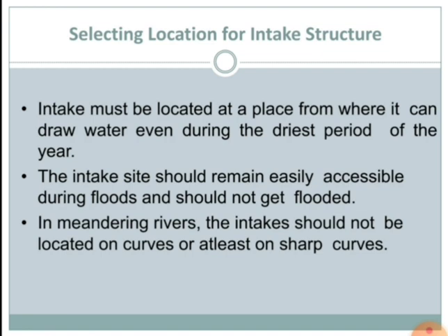Now, the intake site should remain accessible during floods and should not get flooded. This is again another important point to be considered. And also, in meandering rivers, the intake should not be located on the curves. If not on the curves, at least it should not be located on the sharp curves. So these are the various points that should be considered while we select the location for an intake structure.